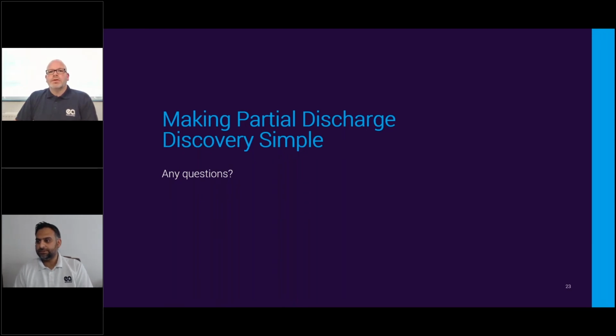Well, thanks, Ramiz. Another one I can see: does LV systems provide TEV or PD? I'm guessing the answer to that is no, but I'll pass over to Ramiz to elaborate. So PD obviously is voltage related. The higher the voltage, the more chances of you detecting and finding partial discharge activity. LV systems generally generate so much noise and there is so little electrical stress that you don't normally find any PD activity in LV systems. But there are other methods of finding issues with your LV equipment, whether that's LV cable monitoring equipment or thermographic surveys.